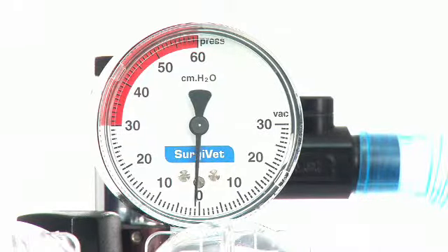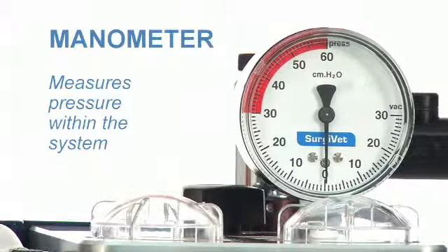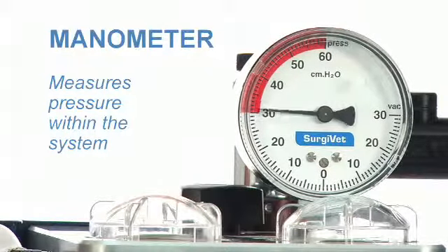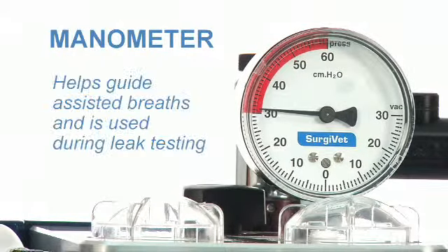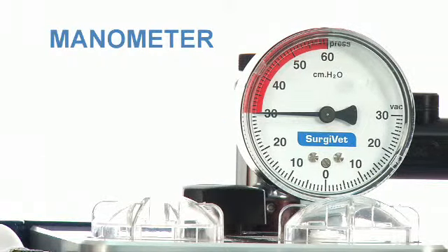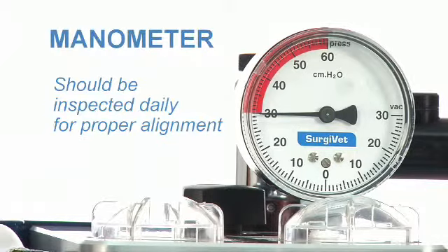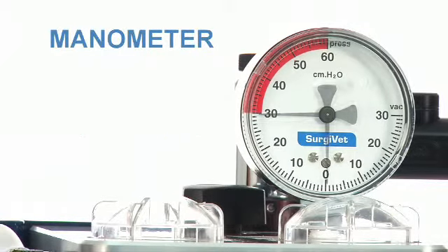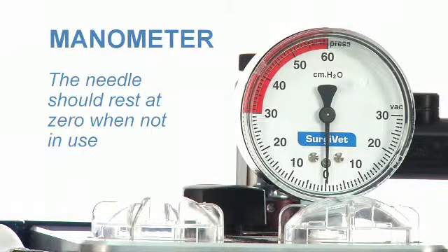Located on top of the machine head, behind the exhalation valve, is the pressure manometer. The manometer is a gauge that measures the pressure within the system. It helps to guide assisted breaths and is used during the anesthesia machine leak testing procedure. The manometer should be inspected daily for proper alignment. The needle should rest at the 0 mark when not in use.